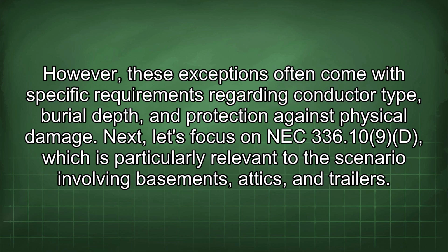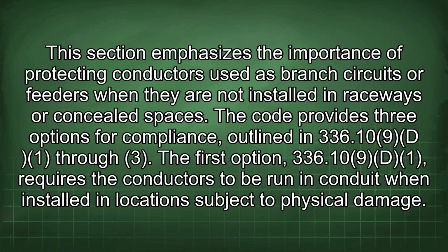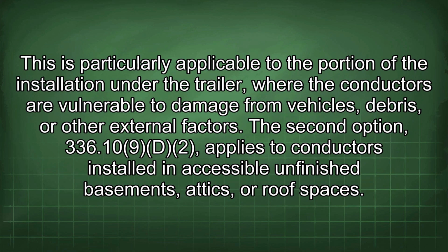Next, let's focus on NEC 336.10(9)(D), which is particularly relevant to the scenario involving basements, attics, and trailers. This section emphasizes the importance of protecting conductors used as branch circuits or feeders when they are not installed in raceways or concealed spaces. The code provides 3 options for compliance, outlined in 336.10(9)(D)(1) through (3). The first option, 336.10(9)(D)(1), requires the conductors to be run in conduit when installed in locations subject to physical damage. This is particularly applicable to the portion of the installation under the trailer, where the conductors are vulnerable to damage from vehicles, debris, or other external factors.